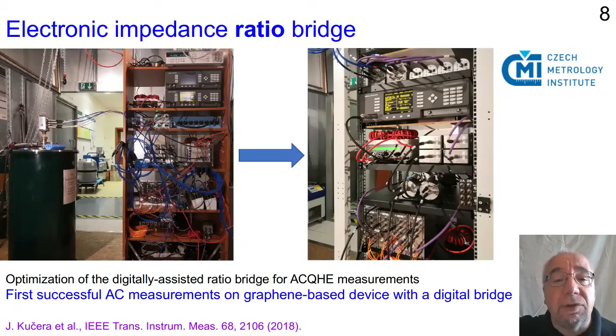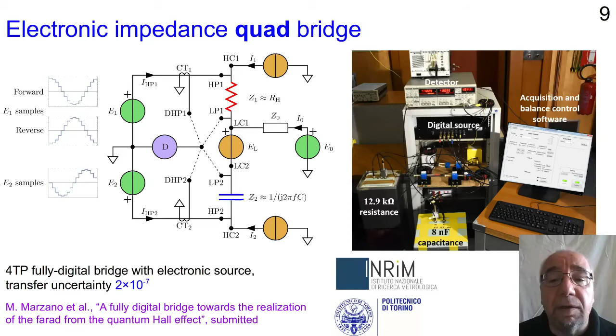To realize capacitance in terms of resistance, you need a quadrature bridge, and this is an electronic impedance quadrature bridge being developed. At the present stage, the bridge, which is a 4-terminal pair, can reach a transfer uncertainty of 2 parts in 10 to the 7. It's particularly simple in its network. And at the moment, it compares resistance and capacitance standards. Of course, the aim is to go to the quantum Hall effect in graphene.